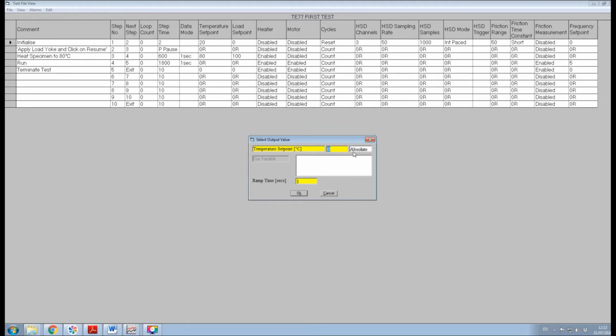Moving on to set points, you will see that the value 0R appears in many places. This stands for zero relative. For example, the temperature set point for step 2 is given as 0R. This means that there is no change relative to the set point in the previous step. So in this case, this temperature set point will remain 20 centigrade. The set point parameter box allows the user to switch between a relative value and an absolute value.